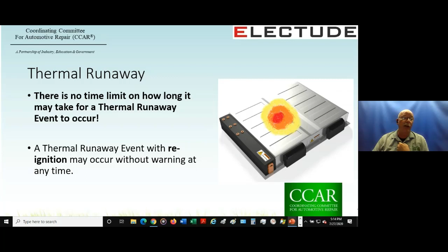But primarily, we're telling everybody that once a thermal runaway event resulting in reignition has occurred, it's not easily going to be extinguished. Firefighting operations may require in excess of 2,500 gallons of water to sufficiently cool and extinguish a high-capacity lithium-ion battery. Firefighting agents such as Class A, B, C, D foam or halon simply do not possess the cooling ability or heat sink ability of water.